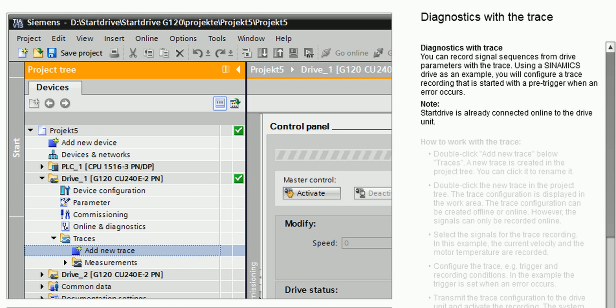Diagnostics with trace. You can record signal sequences from drive parameters with the trace. Using a SINAMICS drive as an example, you will configure a trace recording that is started with a pre-trigger when an error occurs. Note: Startdrive is already connected online to the drive unit.